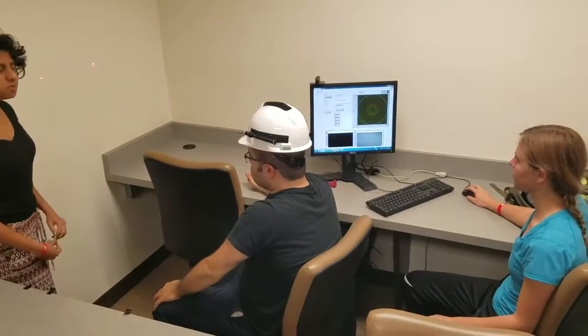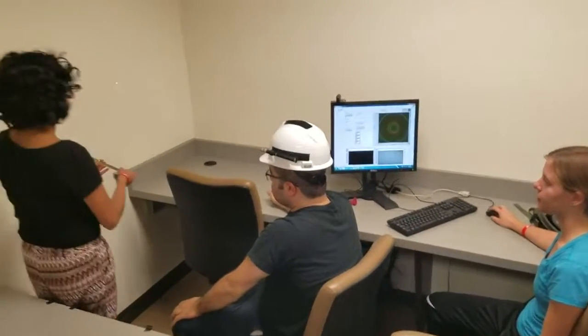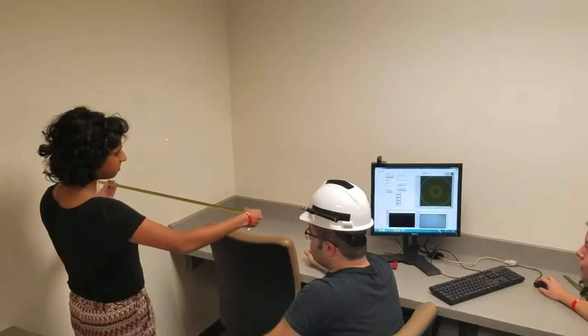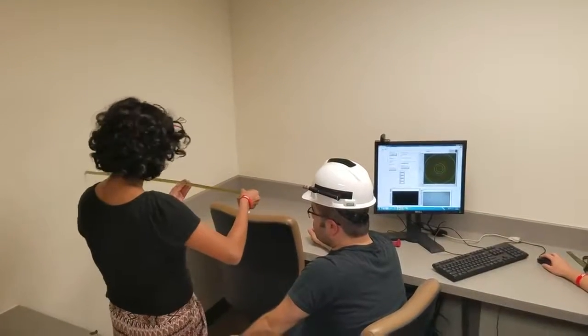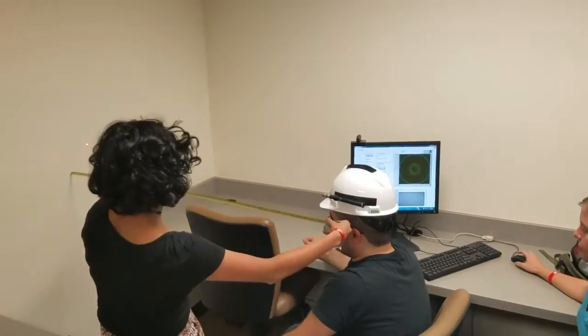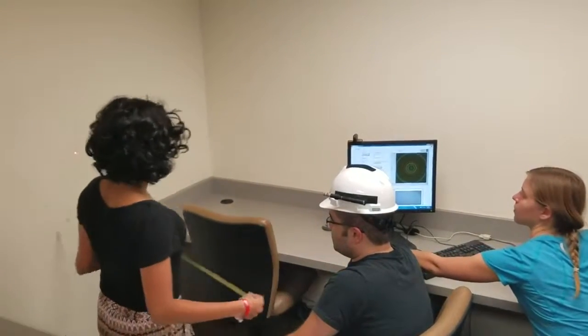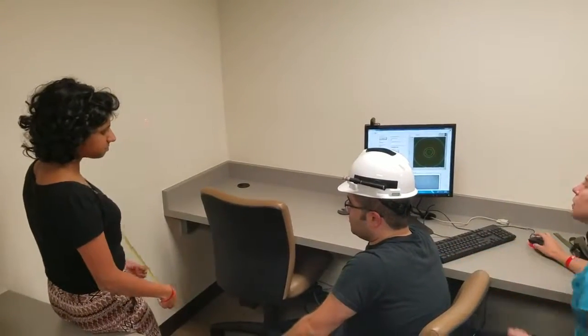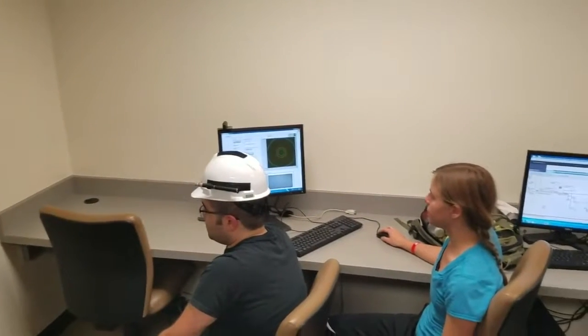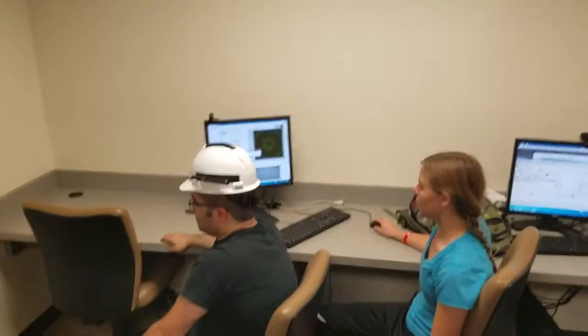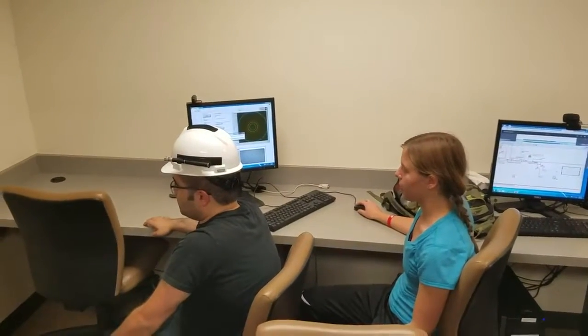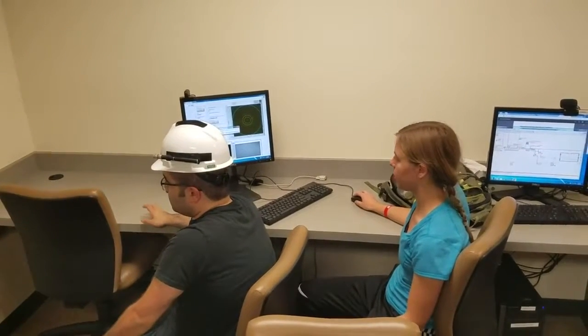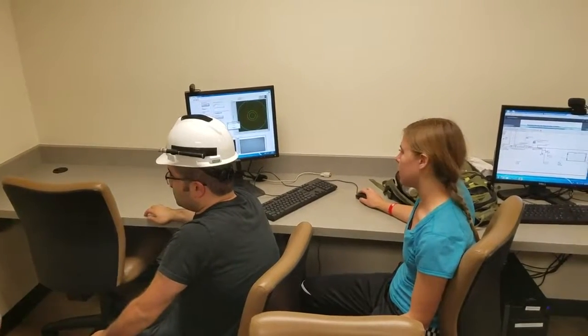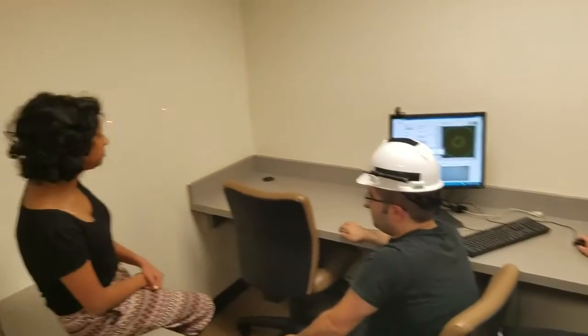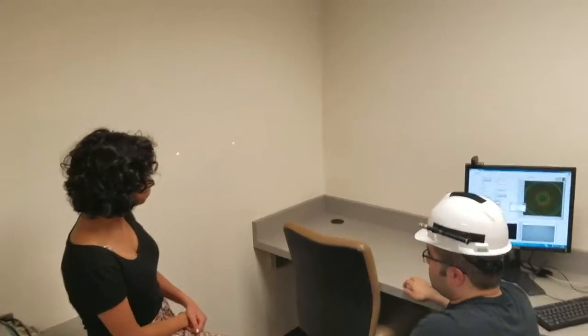In the procedure, we're going to make sure that the patient is sitting 50 inches away from the wall. And the patient is now 50 inches from the wall. We will begin the session. Press start. No, I want to calibrate the camera now because I do not have a current calibration number. Make sure there's 2 lights on the wall that the camera will pick up. Calibrate now.